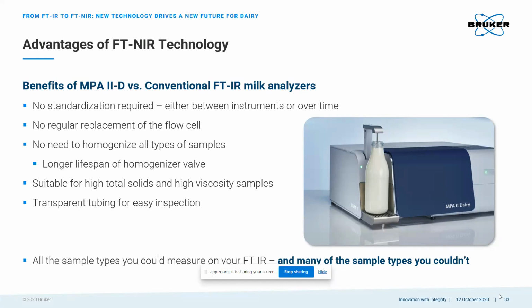We also don't need to homogenize every kind of sample. The homogenizer is only required for raw milk to ensure high repeatability, and this also translates to a longer lifespan of the homogenizer valve. And thanks to the properties of our flow cell, we're also able to measure samples with high total solids. And again, we have the ability to visually monitor our sample tubing. So from raw milk to finished dairy products, you can test the full range along the production chain with just one easy-to-use FT-NIR analyzer.